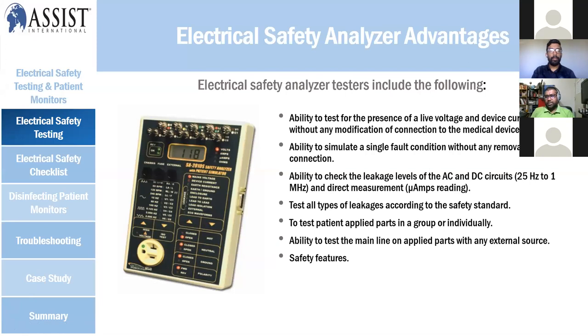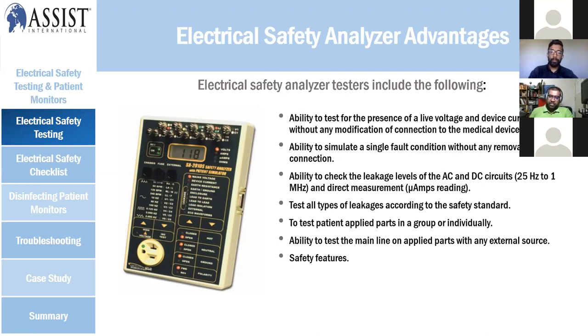Earlier we talked about the electrical safety analyzer in a previous session. When you use an electrical safety analyzer, you are mainly checking leakage current and voltage by connecting the medical device's patient-applied part to the analyzer. It is capable of measuring AC/DC leakage on a circuit and can simulate single fault and normal conditions. It also measures smaller leakage current values. Those are the key advantages of an electrical safety analyzer.